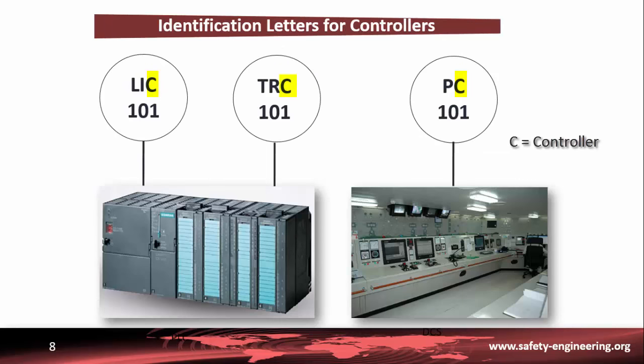When the second or third letter is C, the associated device is a controller. A controller is a device that receives data from a measurement instrument, compares that data to a programmed set point, and sends a corrective signal to an actuator. Local controllers are usually one of three types: pneumatic, electronic, or programmable.